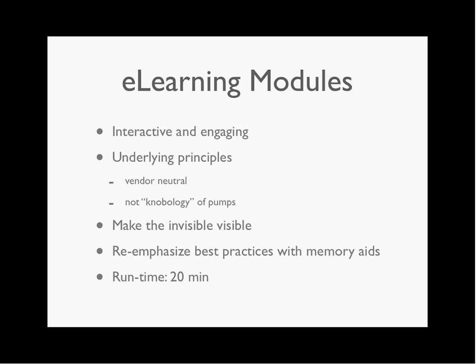So, 2 modules are about secondary IV infusion specifically. They can be viewed independently of each other. A module called Check the Setup really focuses on the physical setup of secondary infusions and the importance of checking your setup primarily above the pump. As Steve mentioned, these modules primarily focus on the issues for gravity-dependent infusion pumps. The other module focuses on the hazards related to secondary and primary infusion sharing IV tubing below the pump, such as administering primary infusion at the secondary rate at the start of the secondary infusion, and vice versa, administering some of the secondary infusion at the primary rate.